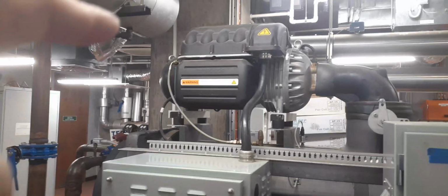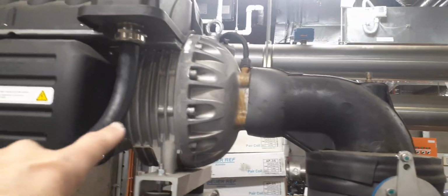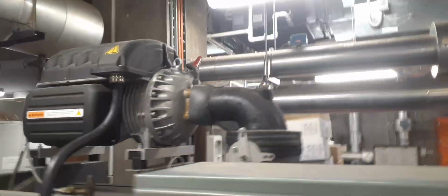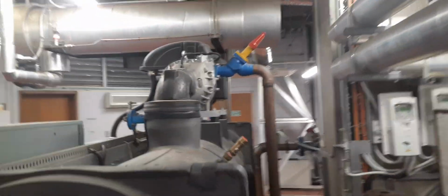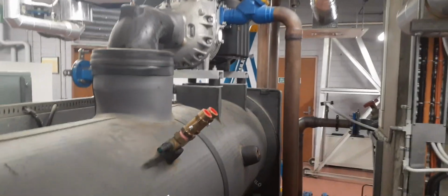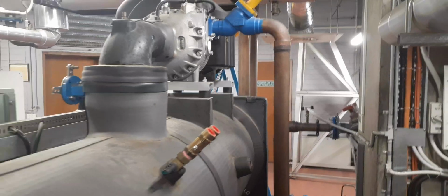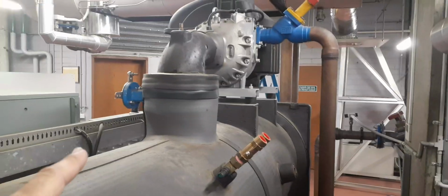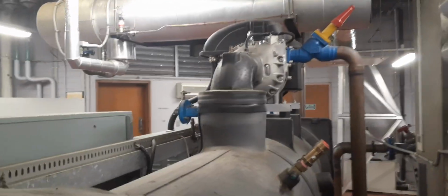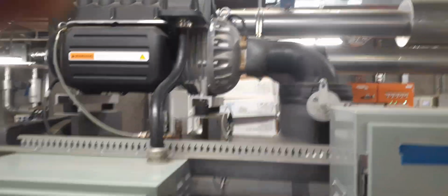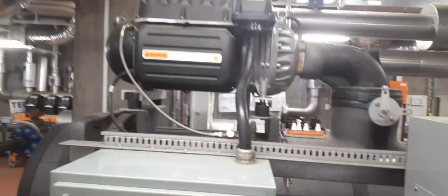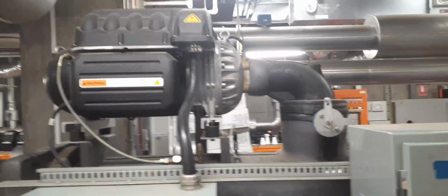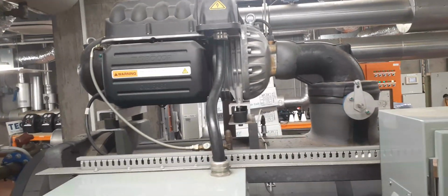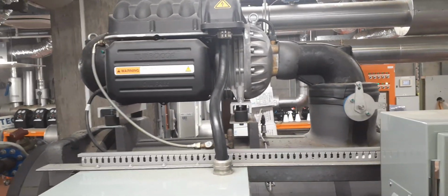And remember, the compressor has a suction pressure and a discharge pressure, so that'll be on the other side. If we come around here, we can see the discharge line coming off, going down into the top of the shell and tube condenser, right? If that pressure drops, the compressor doesn't have to work as hard. And if the compressor doesn't have to work as hard, its amps go down. For every percentage of head pressure decrease, the compression ratio decreases, which we call lift on a centrifugal machine. So that's a centrifugal machine. It's a baby impeller, and these come in 1, 2, 3, 4 compressors on them. They build them here in Australia, and you can actually go to the Melbourne factory and watch them being built.